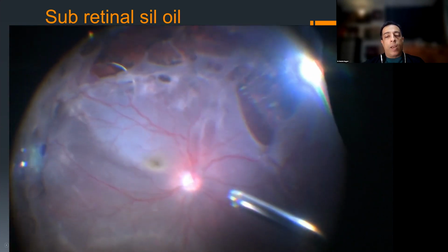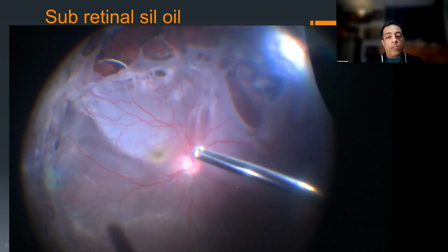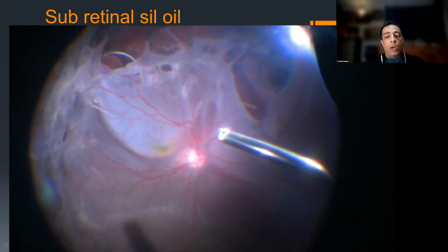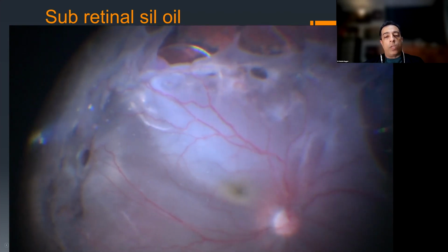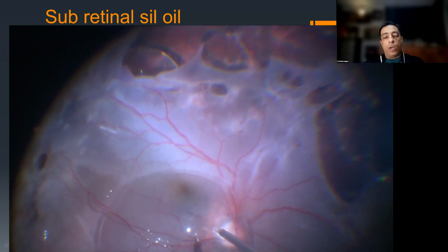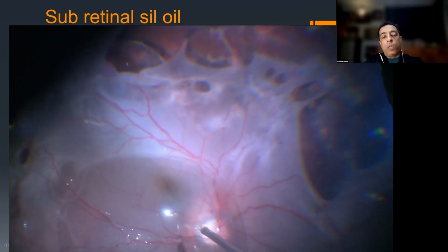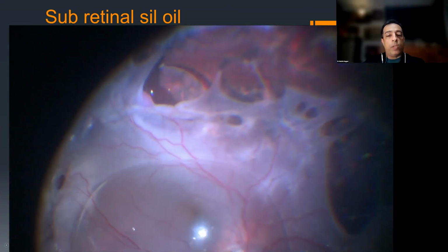There would be saline, there would be PFCL, there would be oil, and these wide angle lenses are just magical. All you have to do is defocus or focus with your foot switch, and you can see through almost every interface as clearly as you can with saline itself, which otherwise was not possible with the previous generation of lenses.